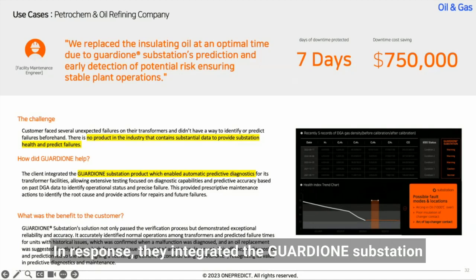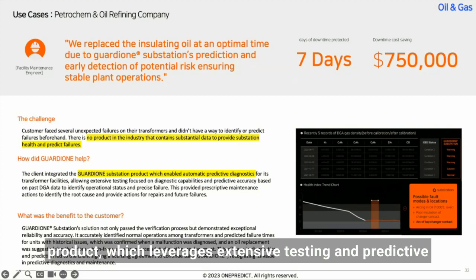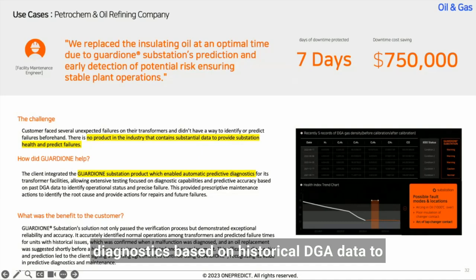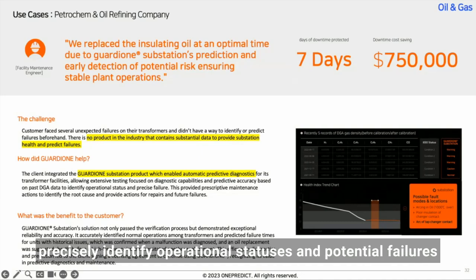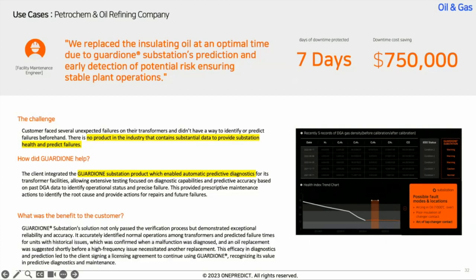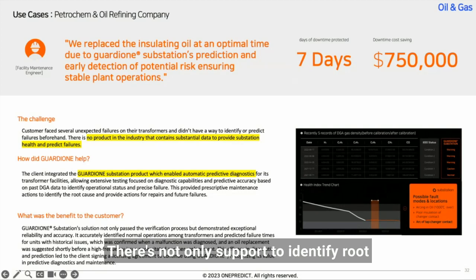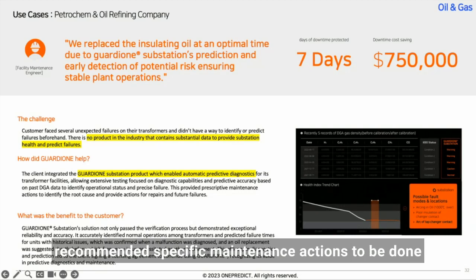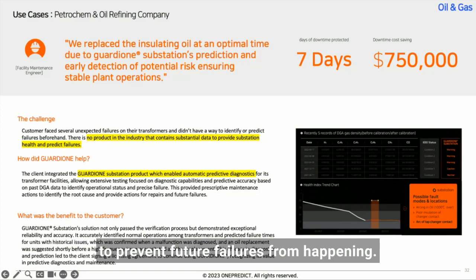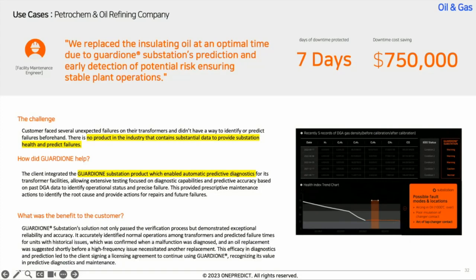In response, they integrated the Guardione substation product, which leverages extensive testing and predictive diagnostics based on historical DGA data to precisely identify operational statuses and potential failures that are forthcoming. This not only supported identifying root causes of the issue, but also recommended specific maintenance actions to prevent future failures from happening.